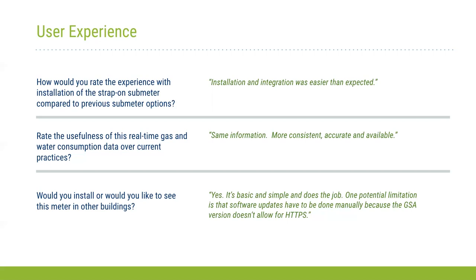And would you install it at other buildings? Yes. It's been easy to install. The Region 7 team has used this, and it's going in at a few other sites. The limit for us is that the chip they have in their device right now doesn't accept HTTPS, which would allow us to remote in and make some changes to it manually. But with the BAS setup that we have that's regional, it's easy for us to just make changes on that from Fort Worth. Otherwise, it would be your normal BAS tech coming to the building, and then they can make local adjustments. So it's really easy, and the limitation for GSA gets canceled out.